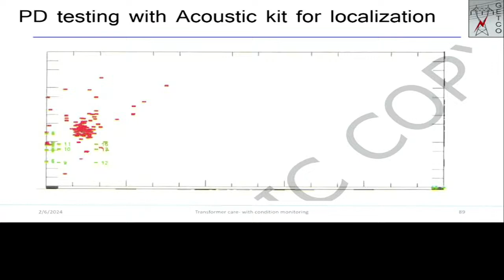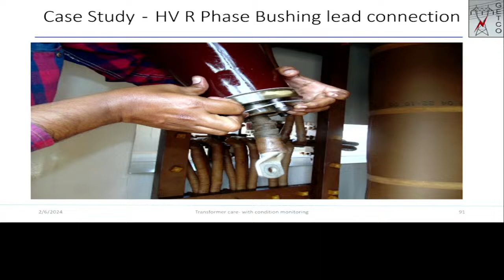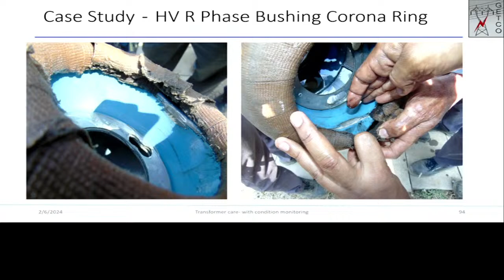So ICT inspection was carried out, but nothing was found in the ICT. So again we were worried about what to do. So we decided, after filtration, to charge the ICT without finding the fault. Okay, it is quite dangerous, but we charged the ICT, and at that time we kept the acoustic PD kit and my PD kit also there. So after charging the ICT, we did the PD survey. There was PD found in B phase, and by acoustic, the area where PD was generated.